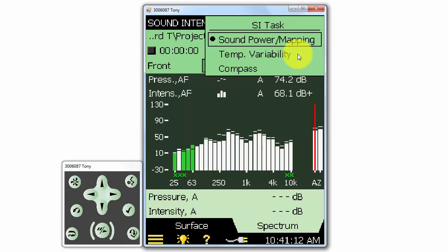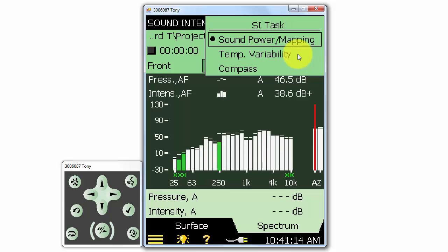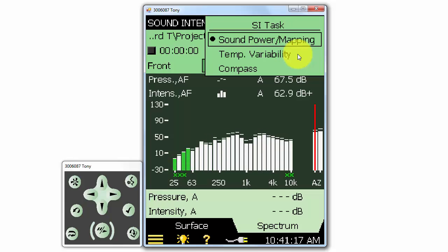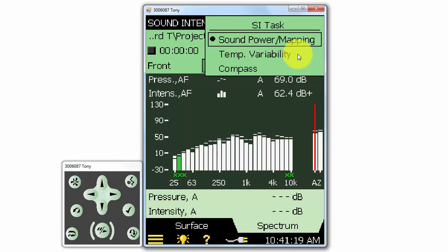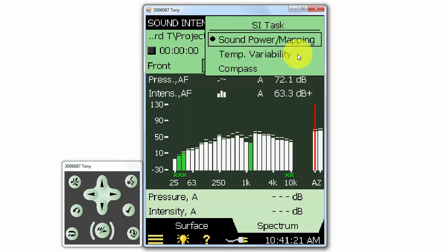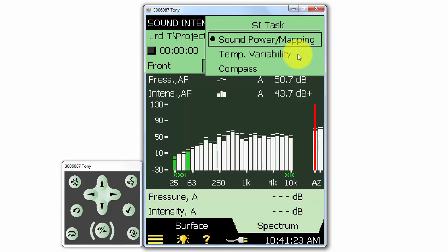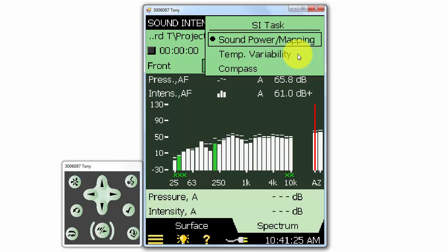We can also check the temporal variability of the system to determine how stationary the source is. This is the F1 indicator in the ISO 9614-1 standard and can be performed as a pretest before you do the sound power determination.